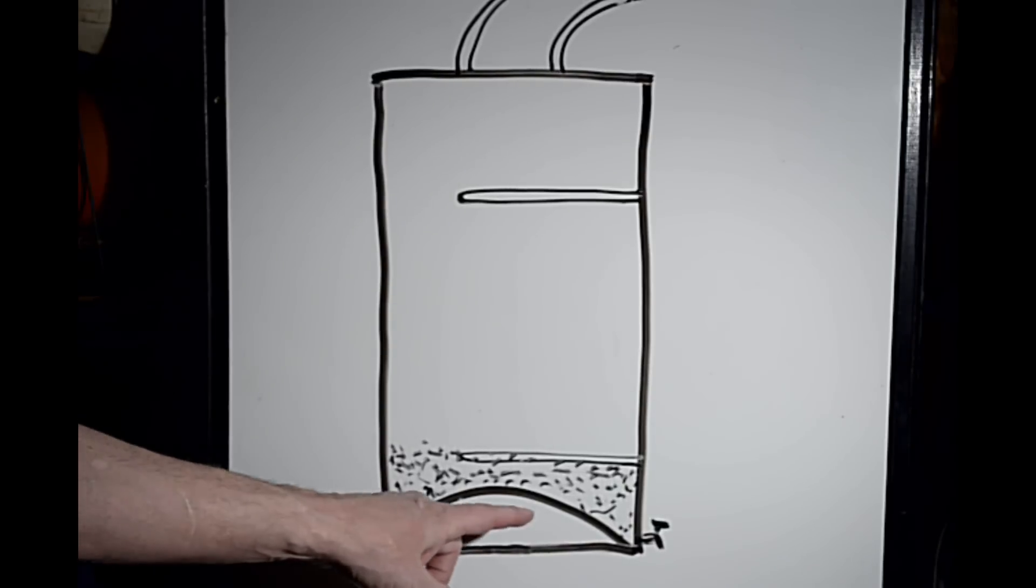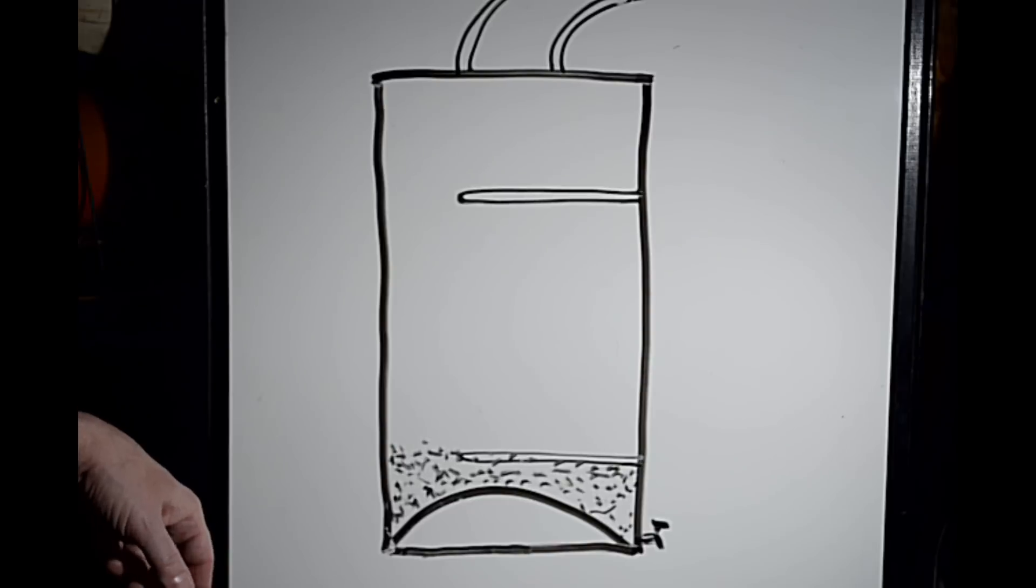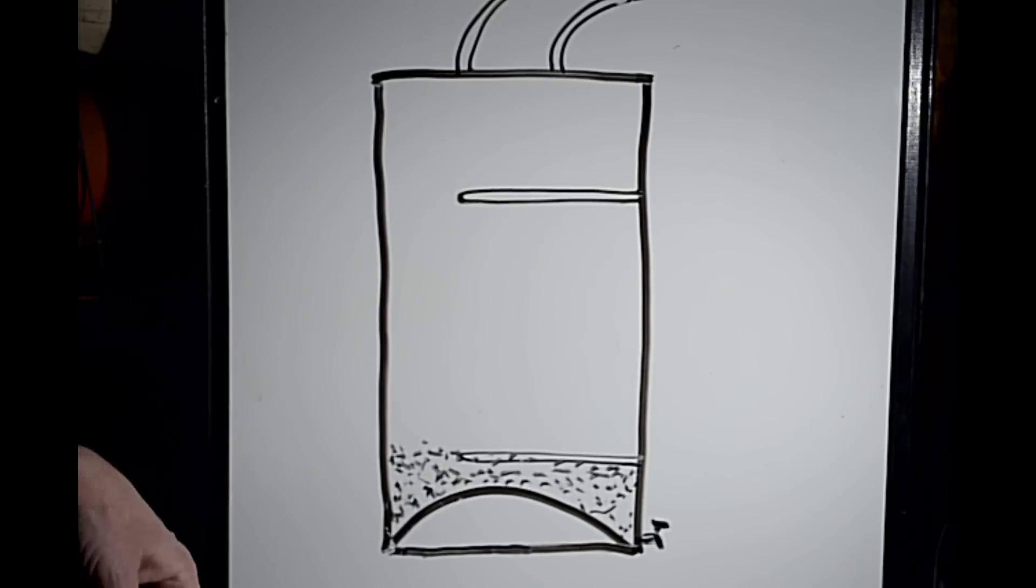As you can see here, the inside of the tank is convex. The lime scale deposits have accumulated all the way up to the heating element. We created some special vacuum wands to use with the wet dry vac to remove these lime scale sediments.